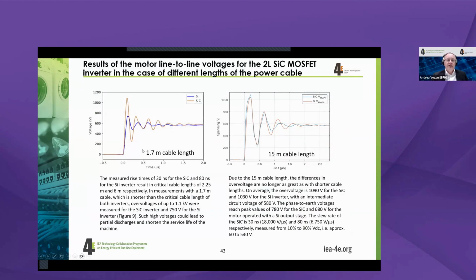From our testing here, with a very short cable length, silicon versus silicon carbide, with switching speeds of like 5 or 6.7 kilovolts per microsecond for the silicon and about 18 kilovolts per microsecond for the silicon carbide, you see that for a short cable length, the over voltage for the silicon carbide can be much higher than the one for the silicon based. But what is important is as soon as you go for a cable length which is over the critical cable length, you will see over voltage in both cases. And they reach the critical value, which is about 2 times the DC link voltage.